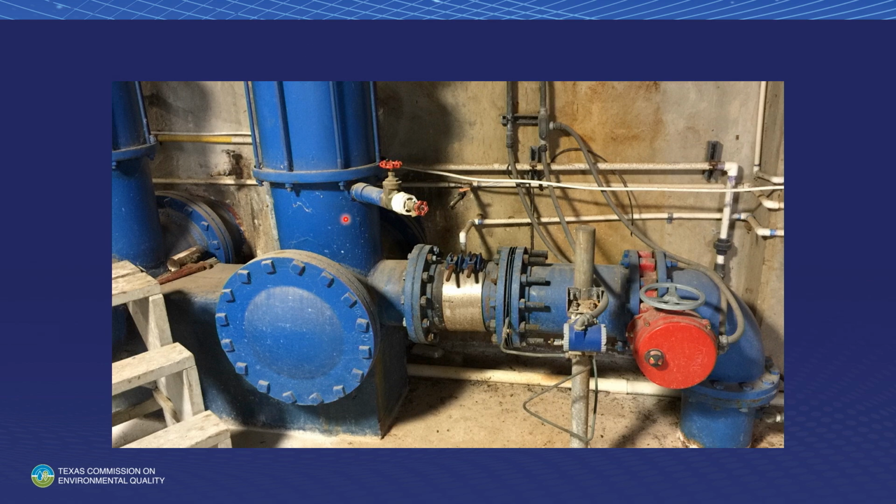Here's the backwash supply line for filter 1. Here's the backwash supply line for filter 2. Water comes out of filter 1, passes through this collar where the sample tap is located into the side of the pipe, where it ought to be located.